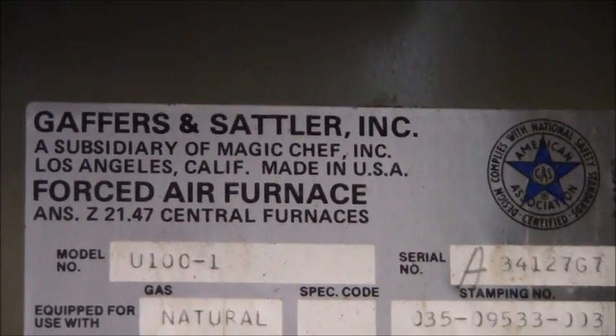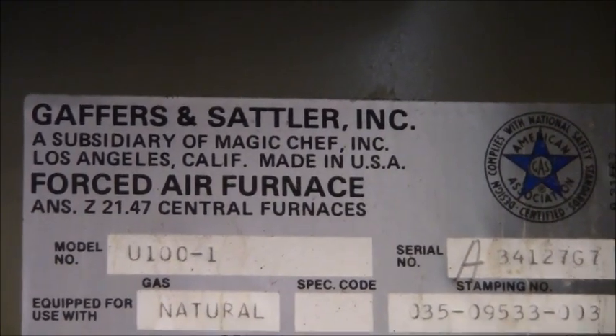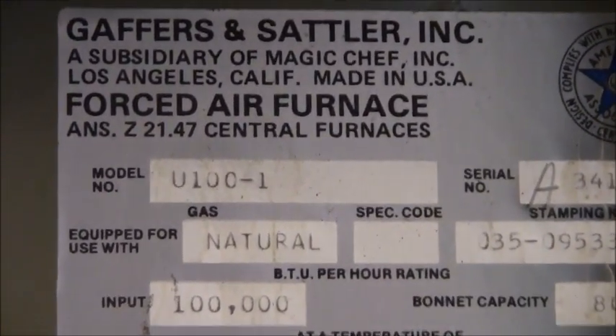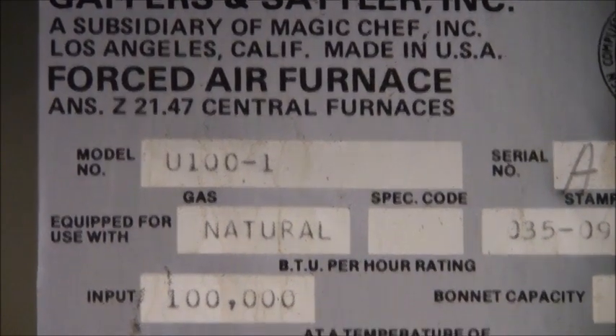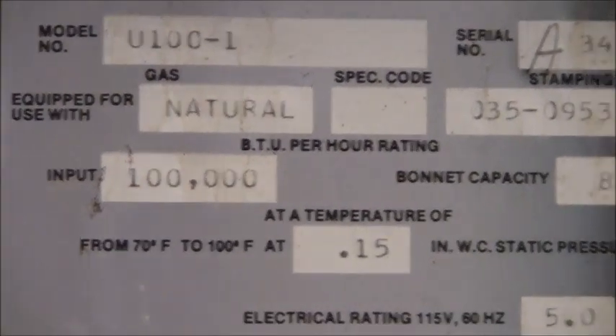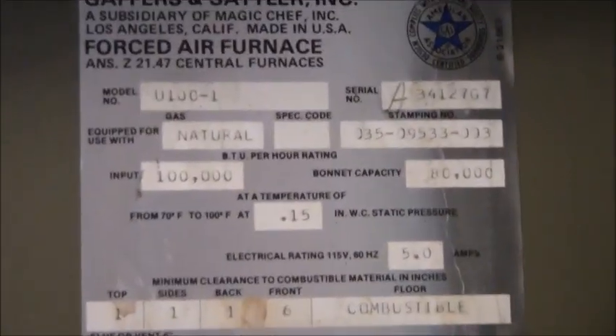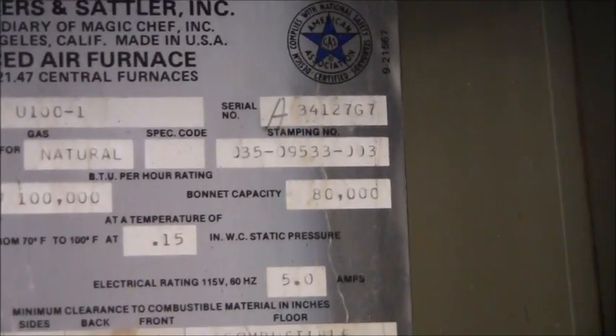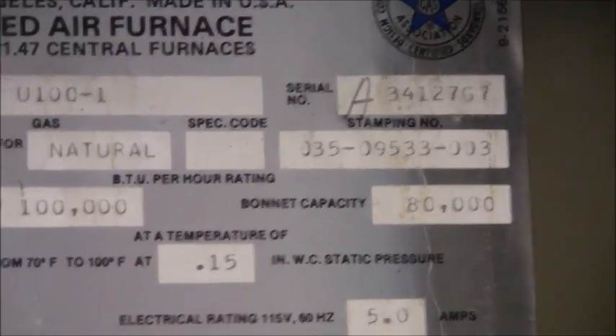Now, on the back of this contraption here, they provide, okay, who's the manufacturer? Let's go through the data nameplate. Here is the furnace data nameplate. So Gaffers and Sattler Inc., Los Angeles, California. There is your model number, U100-1. Natural gas. Input is 100,000. They call it the bonnet capacity, or the output is 80,000. So we know it's an 80% furnace, 100,000 BTUs in, 80,000 BTUs out. You don't even need to do the math, it's already done for you.